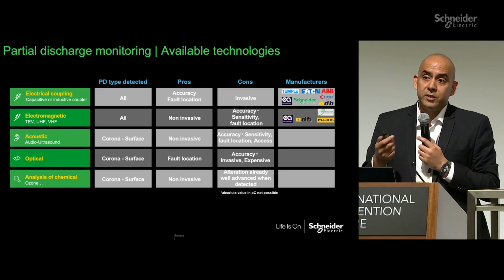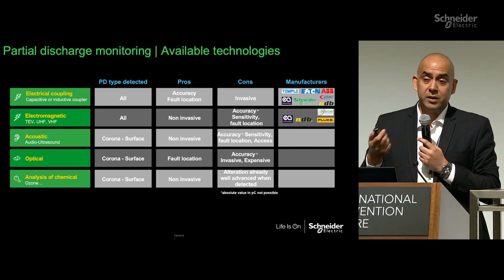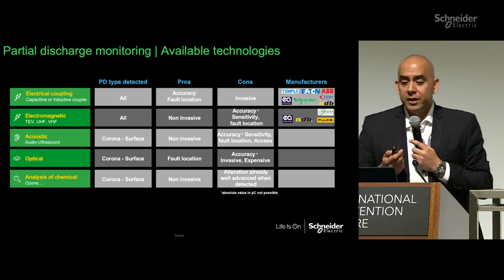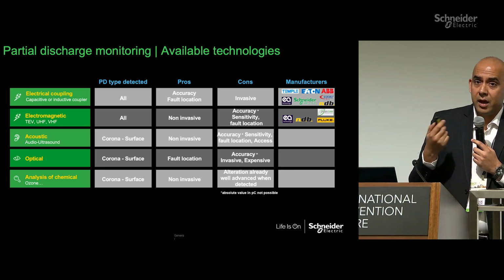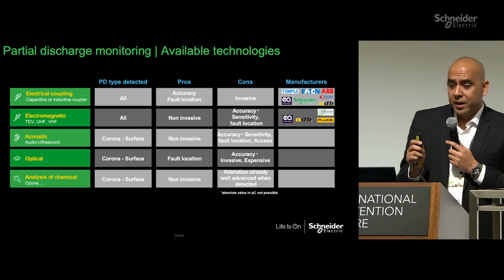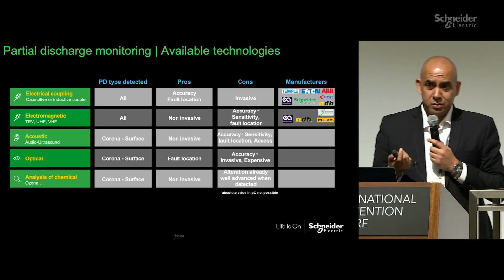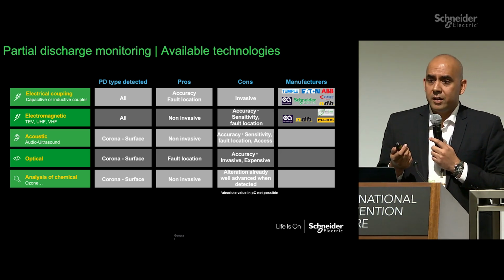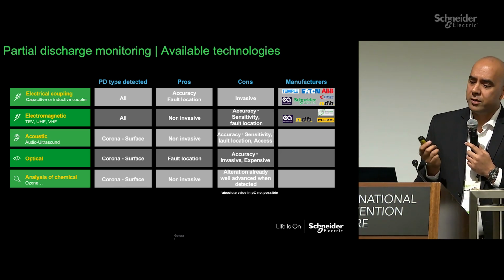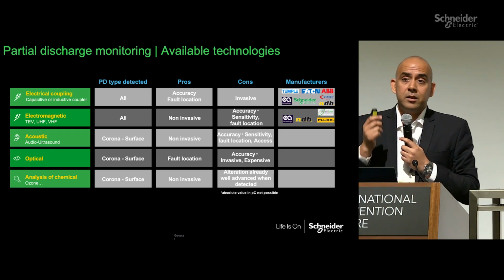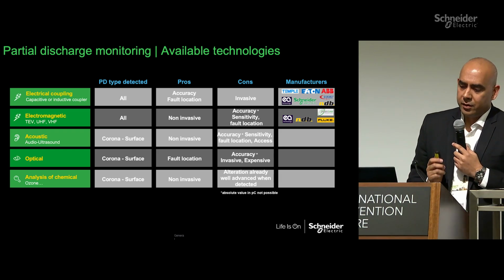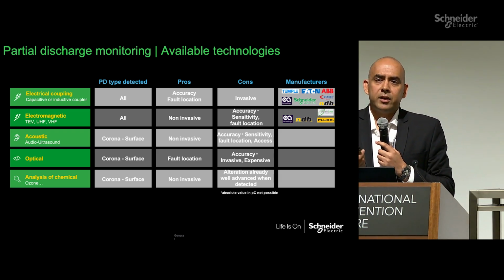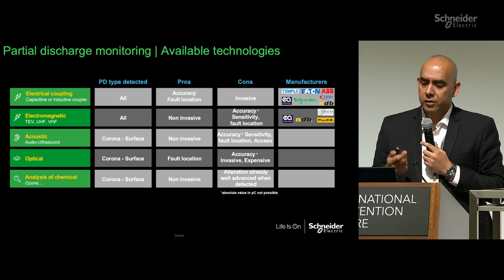You are not able to measure the exact level of partial discharge in picocoulombs. The third is through electromagnetic high-frequency measurement of voltages. Again, this is something which is in use. It is pretty good, but again having issues in terms of sensitivity and in detecting where the fault location is coming in. And of course, in some of our applications, we use this technology also.